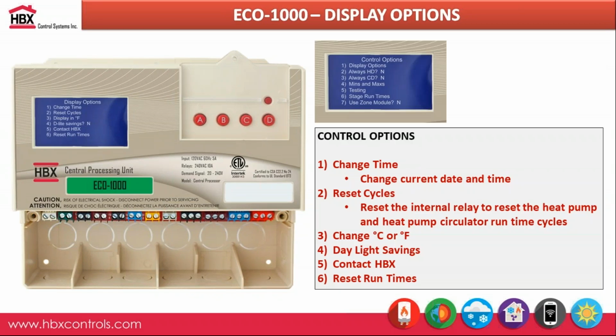So if you were to go into your control options, here is really just access to what you want to see on the display. Here you can change your current time and date. If you want to reset the cycles in terms of your system pump or your heat pump, say something mechanically was installed incorrectly and you were short cycling those heat pumps as well as your backup boiler, you don't want to keep those cycles within your system. Here you can reset those cycles back to 0 as well.